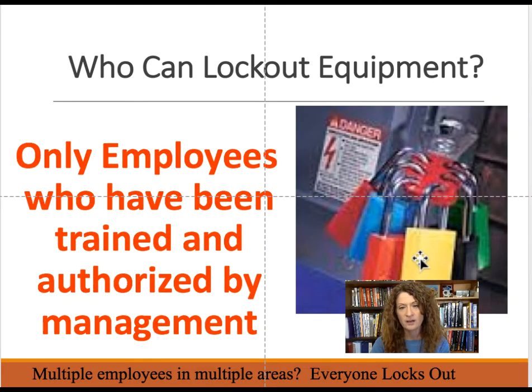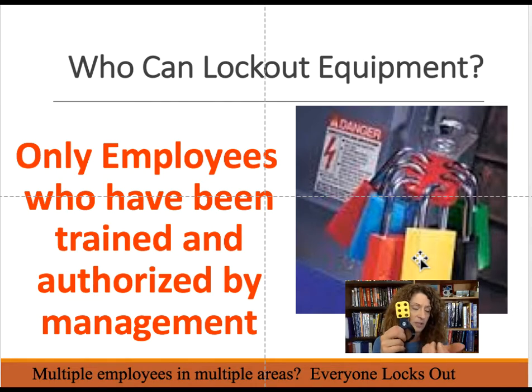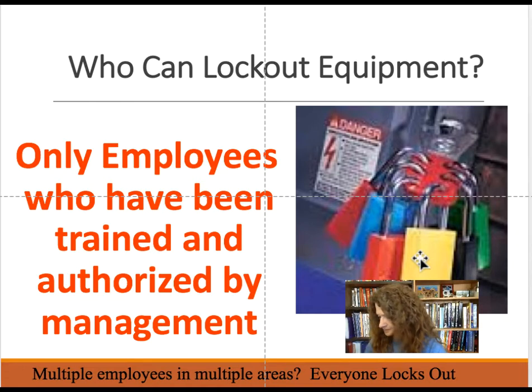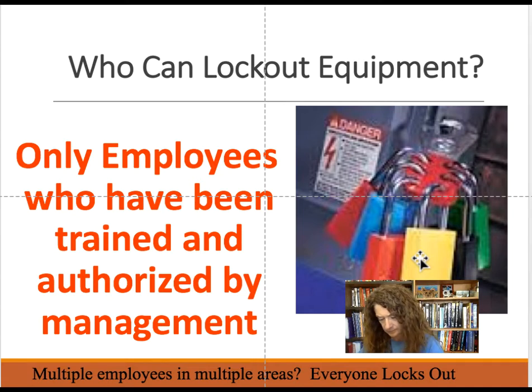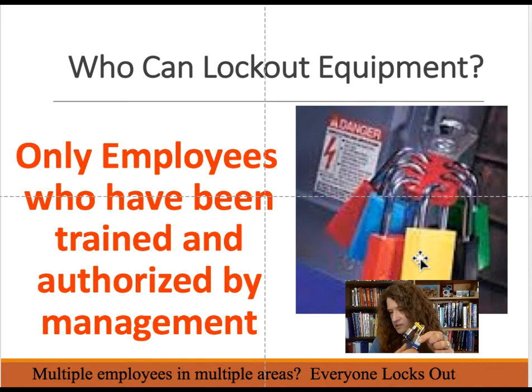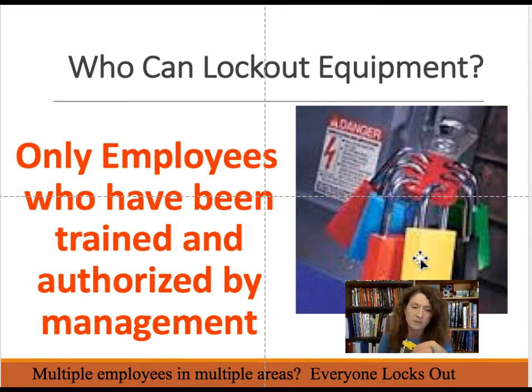When multiple employees are performing work, you use a device where each employee has their own key and their own lock. The system is turned off, locked out, and each employee who is going into that space or may be exposed to the hazard has to lock it up. In hazmat operations, everybody would give their key to a supervisor who would put them in a lockbox — the only time you got your key back was when everybody was out of the space and it was safe to re-energize.